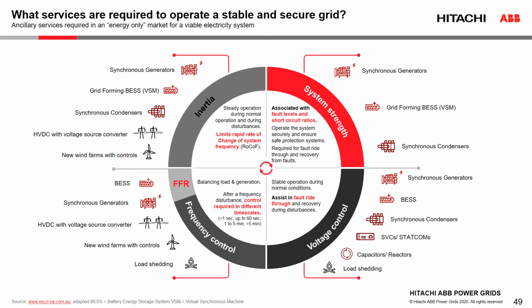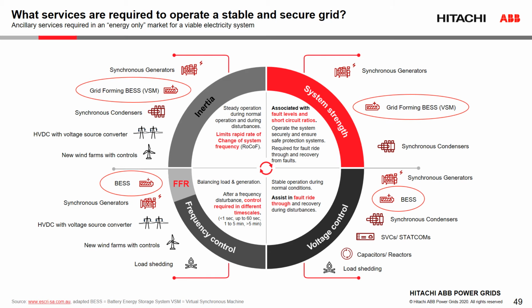So what services do we require to operate a stable and secure grid? Well, as you can see, we need inertia, system strength, voltage control, and frequency control. Synchronous machines provide all of these services, and whilst we have several options in terms of technology to provide voltage control and frequency control, we can only get system strength from synchronous generators, synchronous condensers, and grid-forming energy storage. Now, whilst traditional grid-following energy storage can provide voltage control and very fast frequency control in the form of fast frequency response, or FFR, only grid-forming energy storage can provide inertia and system strength.